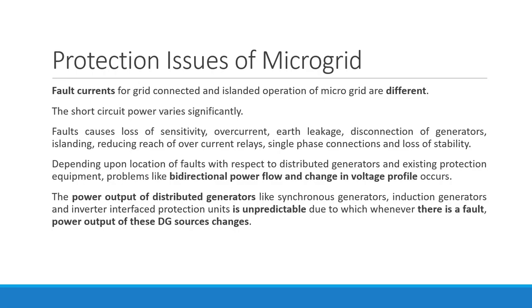Then let us talk about protection issues of microgrid. We talked about how a microgrid can operate in islanded mode, and it can operate in grid connected mode. If suppose there is some fault, it is obvious that the fault current will be different in both modes of operation, that is grid connected mode and islanded mode. The short circuit power is also going to vary significantly.